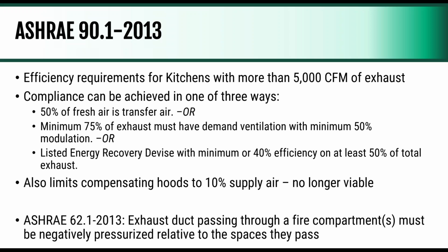Really good example for us is we did a steakhouse downtown Toronto. They had the ducts going up, I want to say it was 13 stories, and they were getting a lot of odor complaints from tenants throughout the building. When we actually measured the exhaust velocities at the filtration unit and then at the roof line, they were significantly different, i.e. there were a lot of holes in that ductwork. And so that's where we put, they call it a booster fan on the exhaust outlet, so that the duct run was negatively pressurized, and that reduced the odor complaints, and everyone was happy. But that's one of the things you'll see later.